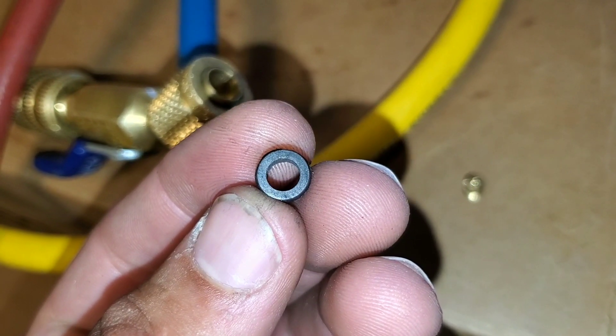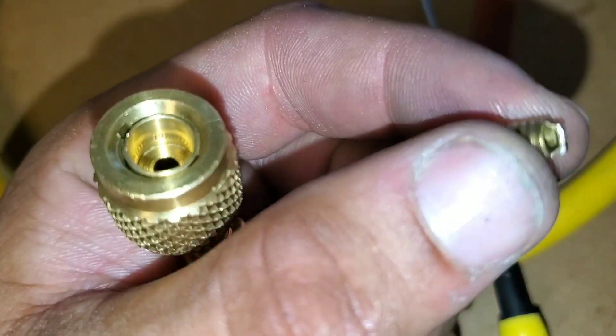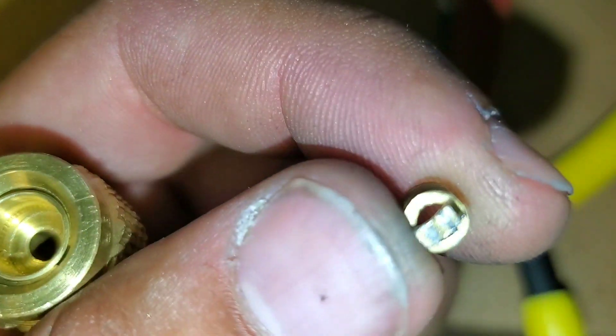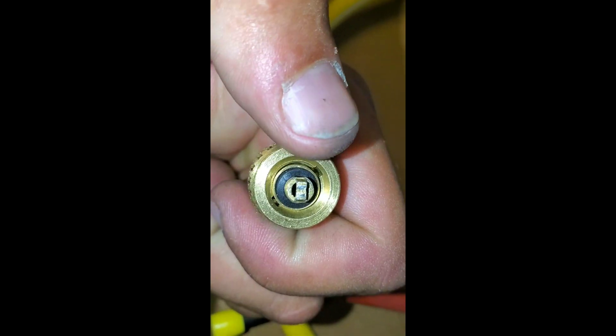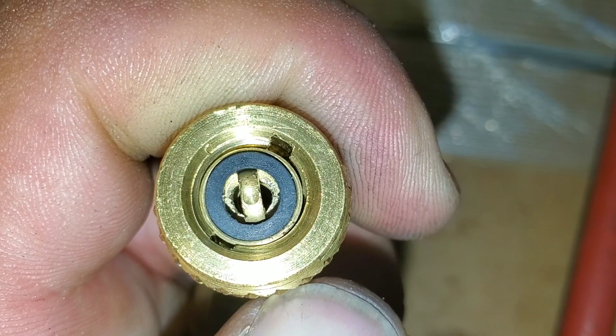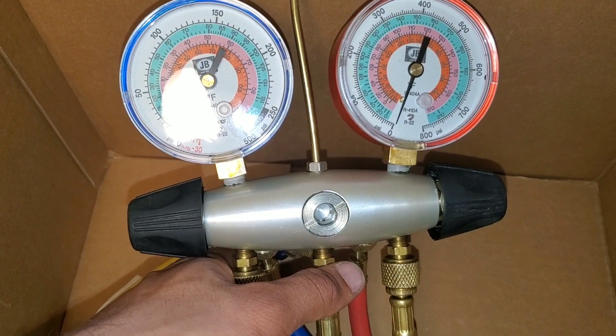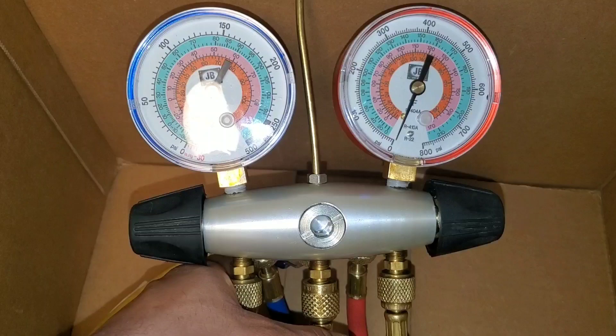My new gasket I'm just going to slide right in. Just for clarification — you can see here that this is threaded, but it doesn't actually tighten down to the holes; there's no threading at the bottom. Basically you're going to put the gasket inside and slide the depressor right into it. You're just going to push it in and set it — you're not going to twist it. It should look nice and flush once you're done. Just doing these simple things will prolong the use and life of your gauges and your manifold. If this video was a help or informational, please subscribe.